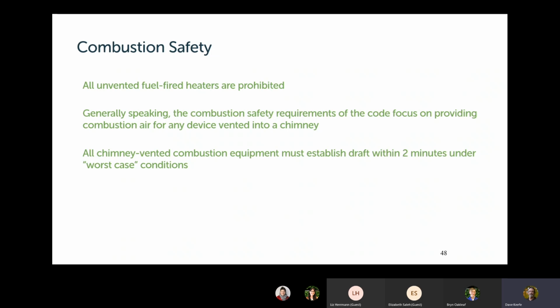And one of the requirements is all chimney vented combustion equipment must establish draft within 2 minutes under worst case conditions. This is a specific performance test, and the way it's done is that the building is sealed up as tight as it can be, and all the exhaust fans in the building are turned on. So that's the kitchen exhaust, the bathroom exhaust, the clothes dryer, central vac, if there is one and it's vented to the outside. And then under those conditions, the combustion appliance that's hooked to the chimney is fired up, and it has to overcome the suction developed by those exhaust devices. So that's a specific performance test, and basically says that when all of the exhaust fans gang up and try to suck air down the chimney, the assembly has to be such that they can't do that.